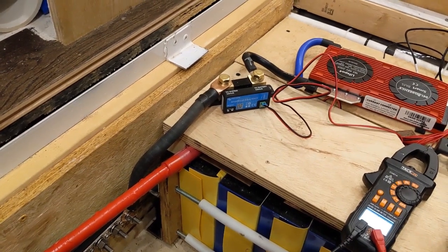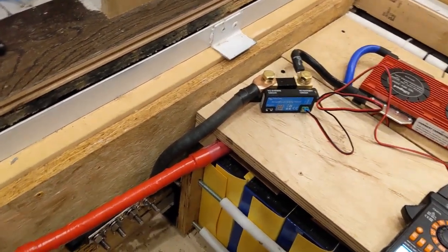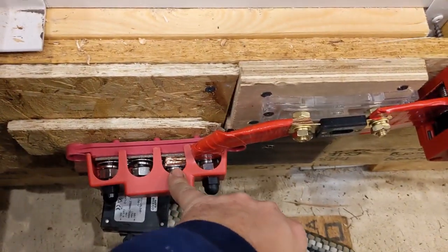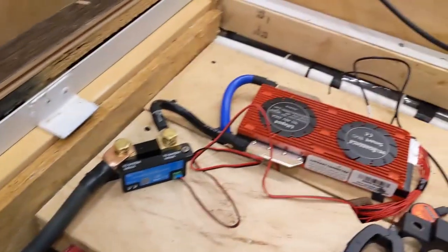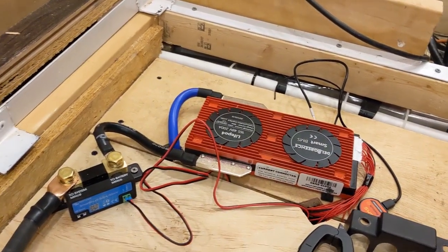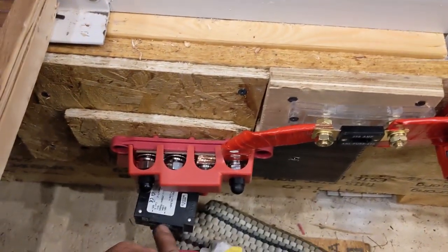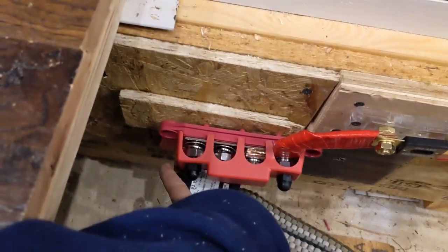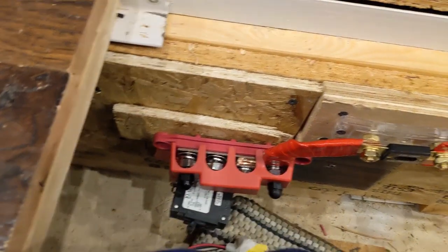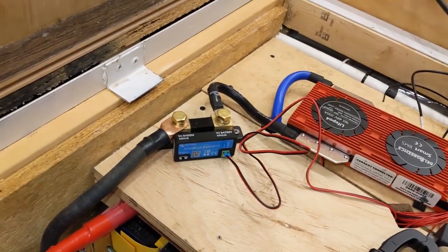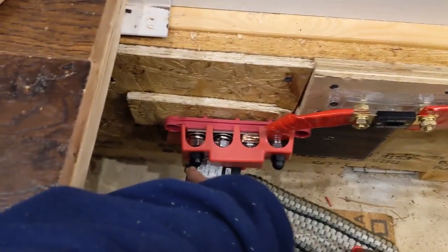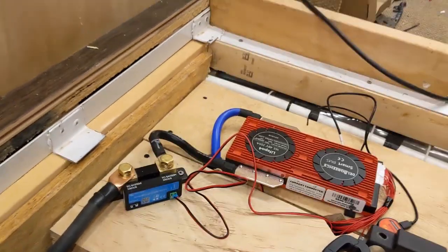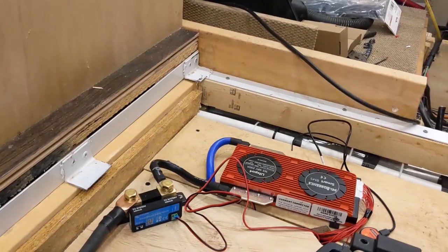So what I'm going to do now, I actually already did. I flipped the switch here and I tested from this side of the breaker over to the blue terminal there and still got 54.1. The next thing I'm going to do is flip this DC breaker into the on position, and I'll test from where the inverter is going to connect down here to the same spot, after which I'm going to test the overall resistance between that location and that one, just to make sure I don't have any high resistance connections. Should be almost negligible resistance.